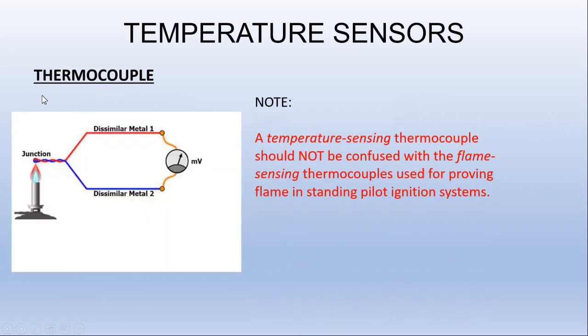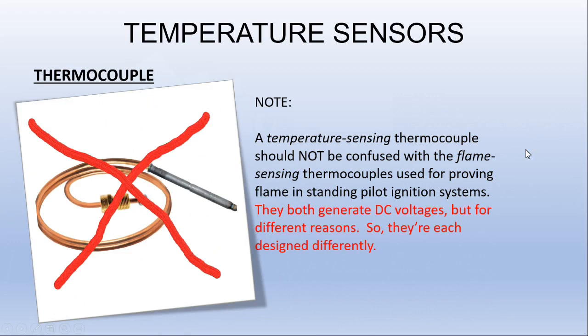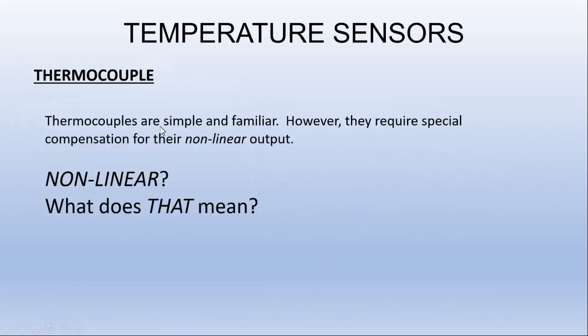Something that should be clarified here, in this illustration, you have a flame, two dissimilar metals, and a millivolt output. This represents a thermocouple that would be used in a pilot ignition circuit. Temperature sensing thermocouples should not be confused with the flame sensing thermocouples used for proving flame in standing pilot systems. They both generate DC voltages, but for different reasons, so they're each designed differently. Thermocouples are simple and familiar. However, they require a special compensation for their nonlinear output.